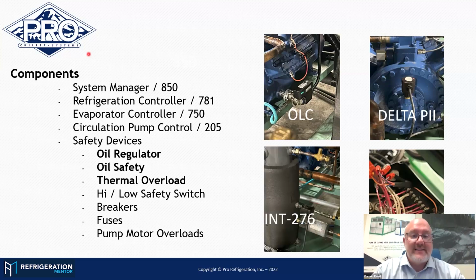The things feeding that safety relay would be, for example, the oil regulator. We use the OLC oil regulator, mounted into the side of the compressor. It's got a little series of lights on it. If it's green, it's happy. If it's not green, it's not happy. That's the simplest way I can describe that. There is a sight glass on the front of it, so you can monitor the oil level.